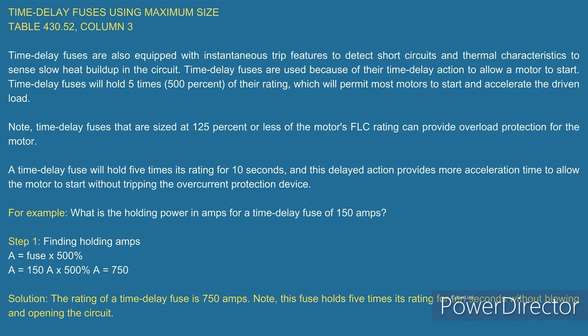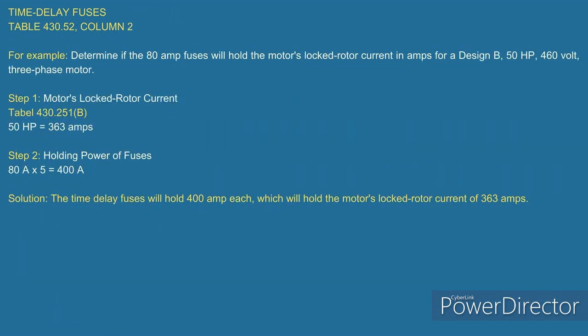All right, now look at this. It tells you a time delay fuse will hold 5 times its rating for 10 seconds. So if I take 150 amps at 500%, that's going to give me 750 amps. I'm just doing the same thing. I'm not really changing anything here. So if you look here, same calculation. I came up with 80 amp fuses. What do they hold? 400 amps, for a 50 horsepower, 460 volt, three phase motor. The locked rotor current was 363 amps. It takes care of it. Now, nice.